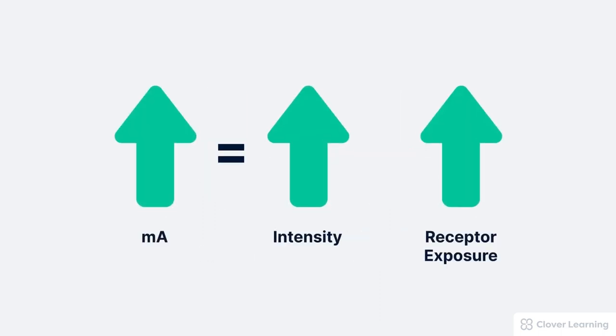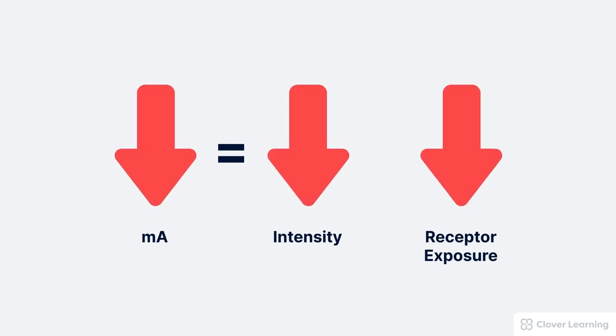Tube current, or the MA, also affects the receptor exposure in the exact same way that it affects intensity. If we increase the MA, the receptor exposure also increases by the same amount. So if we double the MA, the number of x-rays striking the receptor, that's the receptor exposure, will also double. And of course, the opposite is true. If we decrease the MA, this decreases the intensity and the receptor exposure by the same factor.